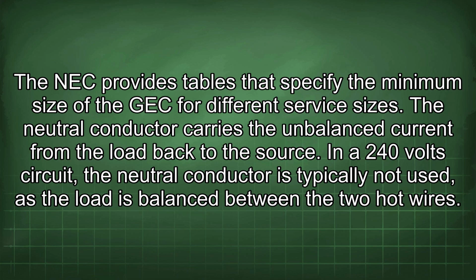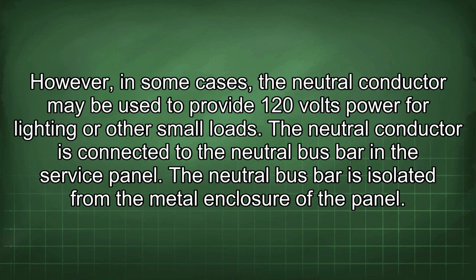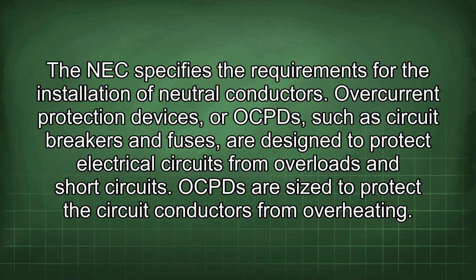The neutral conductor carries the unbalanced current from the load back to the source. In a 240-volt circuit, the neutral conductor is typically not used, as the load is balanced between the two hot wires. However, in some cases, the neutral conductor may be used to provide 120 volts power for lighting or other small loads. The neutral conductor is connected to the neutral bus bar in the service panel. The neutral bus bar is isolated from the metal enclosure of the panel. The NEC specifies the requirements for the installation of neutral conductors.